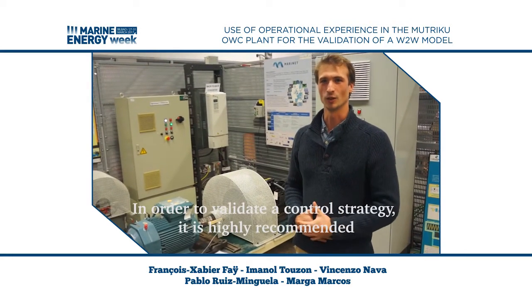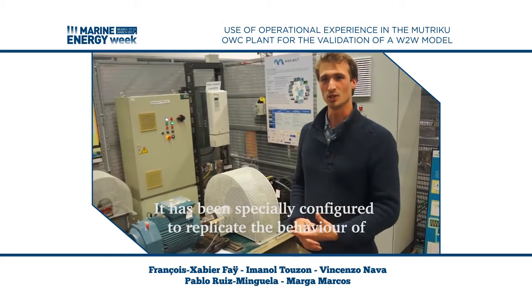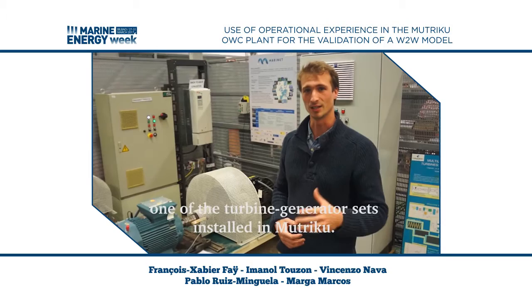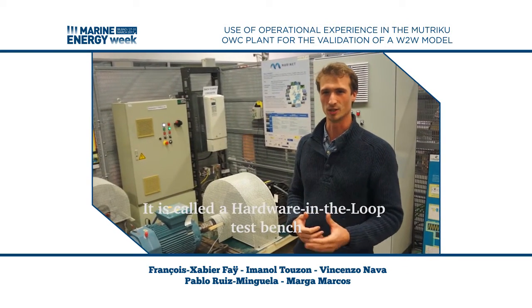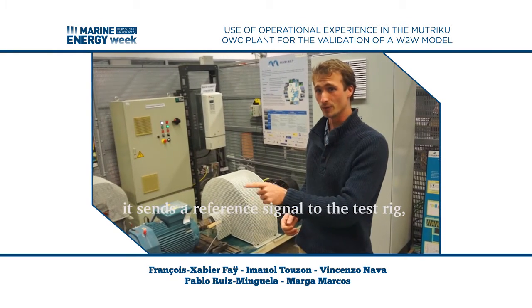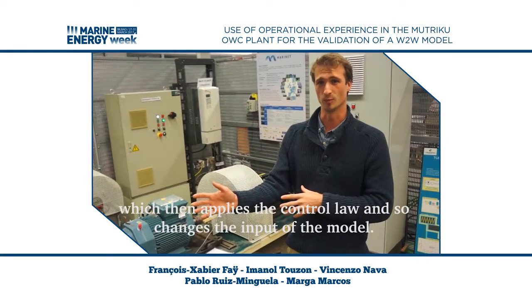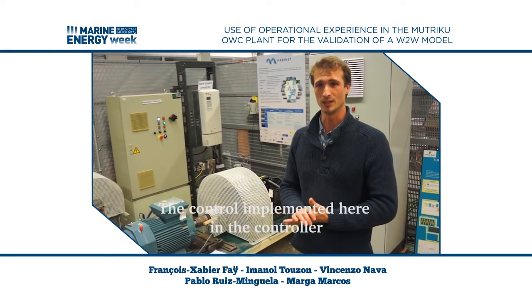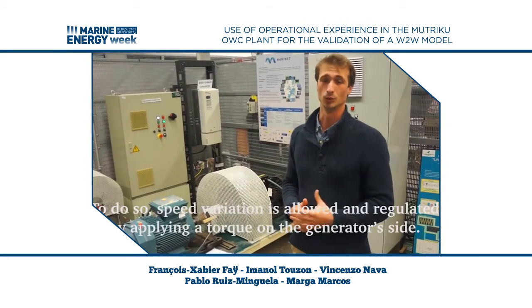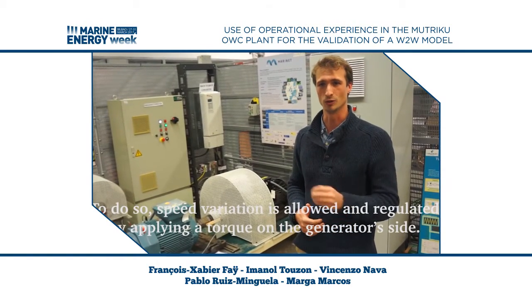In order to validate a control strategy, it's highly recommended to use an electrical infrastructure like this one. It's been specially configured to replicate the behavior of one of the turbine-generator sets installed in Mutriku. It's called the hardware-in-the-loop test bench, because when the model of the plant is running in real time, it sends a reference signal to the test rig, which then applies the control law and changes the input of the model. The control implemented in the controller is designed so that the turbine operates at its best operating point. To do so, speed variation is allowed and regulated by applying torque on the generator side.